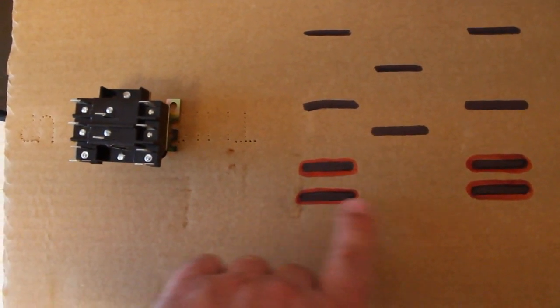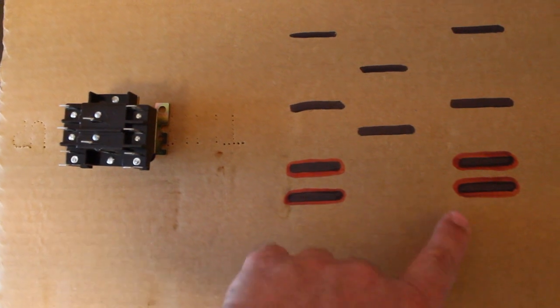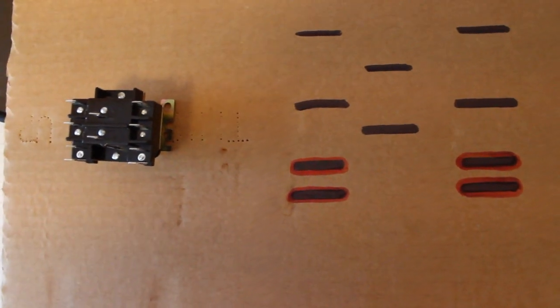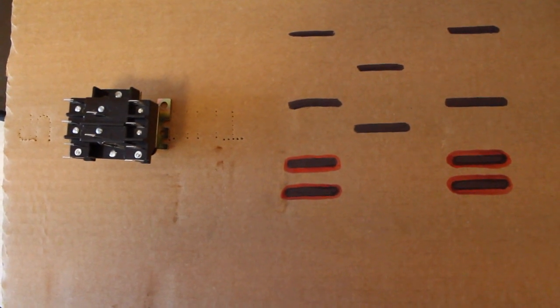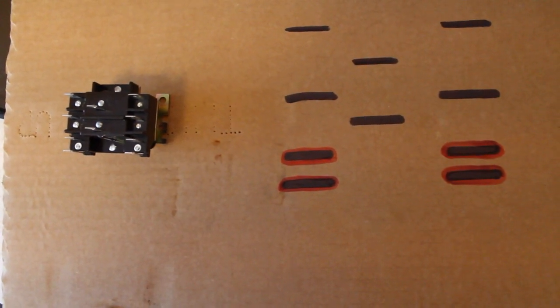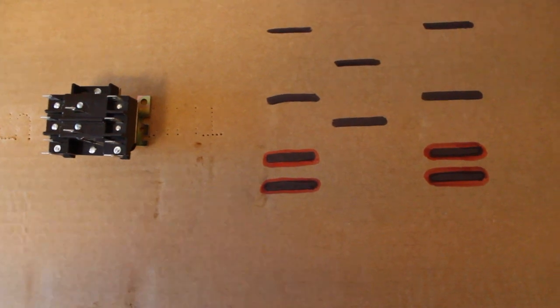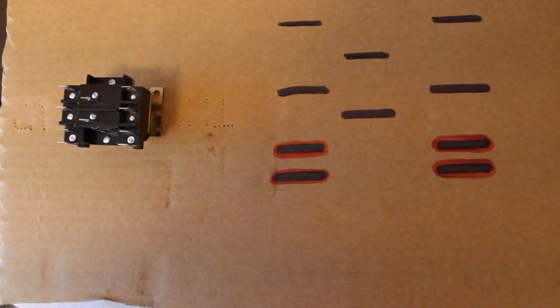On one side, you would have your common, either one, and on the opposite side you'd have your hot, 24 volts on this particular relay. Of course, some coil voltages are 120 or 240, but for most of mine, it's 24 volts. So that is your coil voltage there in the red.